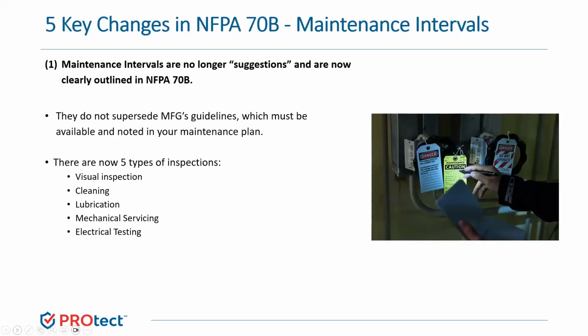Absolutely. We will break these changes into 5 key changes and go through them one by one. The first is on maintenance intervals, which are no longer suggestions but are now clearly outlined in NFPA 70B. First and foremost, it's important to understand that maintenance intervals outlined in the 70B tables do not supersede any manufacturer guidelines. They only provide guidance in the absence of information from a manufacturer. You should always consult manufacturer recommendations and guidelines first, and ensure you understand, maintain, apply, and train on the manufacturer guidelines for each electrical component in your system.